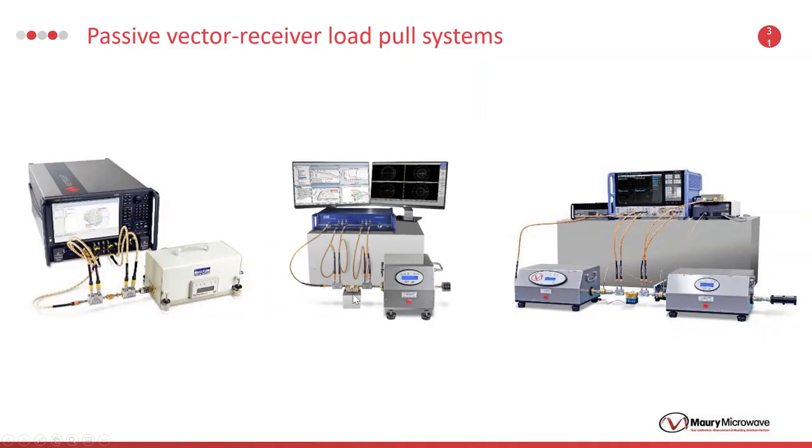So the power is important. If we don't have enough power, we need to add a driver. This seems to be a high power device, and to be able to drive it, we need a source tuner, okay? So these are the typical setups that we can use for load pull. It can be a very simple, medium, or high power setup.